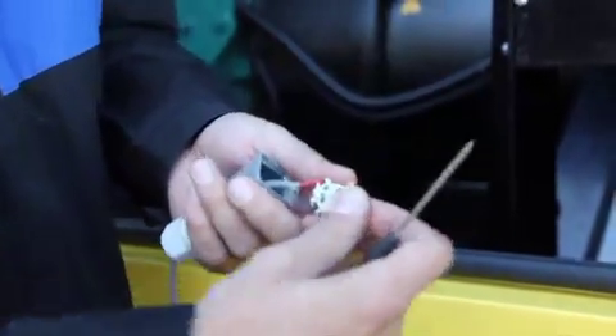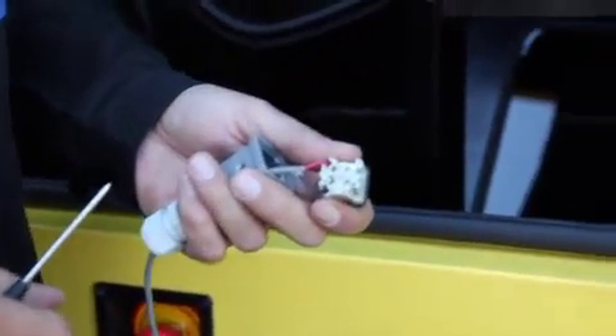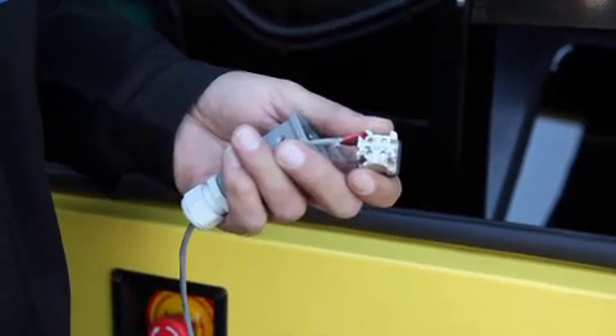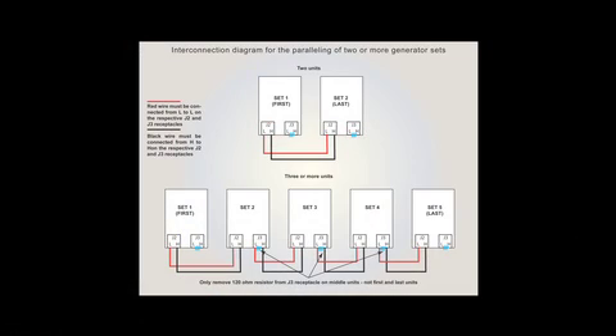Step 6: Verify the interconnecting black and red wires between receptacles J2 and J3 on each of the sets are connected in identical sequence, with CAN-L red wire to Terminal 1 and CAN-H black wire to Terminal 2. Review the diagram demonstrating the black and red wiring between receptacles J2 on two units, and J2 and J3 when paralleling more than two units. Note the removal of the 120 ohm resistor on the middle sets from J3.